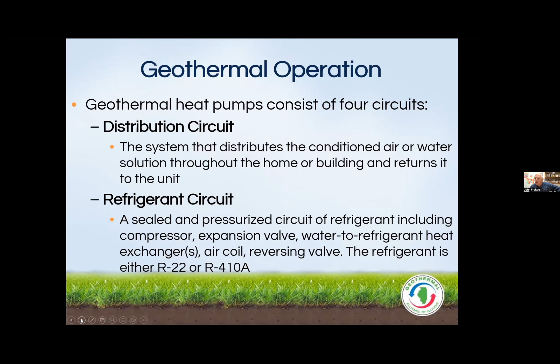The second circuit is contained within the unit—that's the refrigerant circuit. Remember the picture of my unit 8 feet from where I'm sitting? That's the refrigerant circuit. It simply takes the energy flowing through the closed loop system, takes about 6 or 7 degrees out of that water in heating mode, sends it back down to the earth, then multiplies or expands that heating through the refrigerant circuit to make heat for the home. It reverses itself in summer to provide air conditioning—basically working in reverse, rejecting heat into the ground.